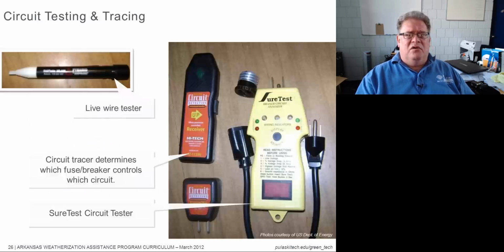Here in the top left-hand corner, we have a non-contact voltage tester. Everybody should be carrying one of these. There is no reason to get shocked by a live wire unless you just didn't see the wire there. But these live wire testers, you can get them close to an AC circuit, even down as low on some of them as 24 or 48 volts, and they'll sing at you.